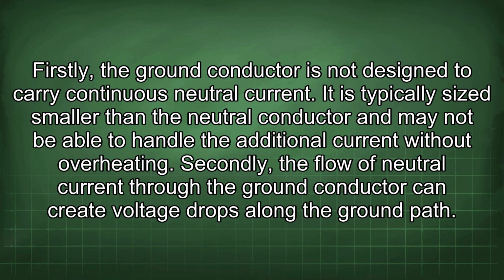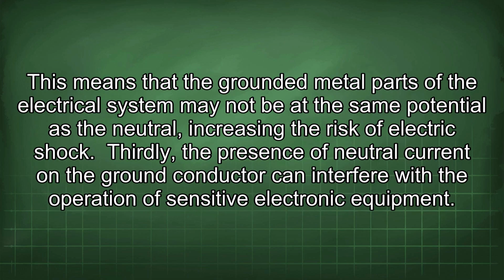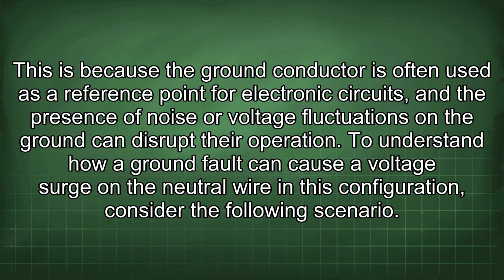Firstly, the ground conductor is not designed to carry continuous neutral current. It is typically sized smaller than the neutral conductor and may not be able to handle the additional current without overheating. Secondly, the flow of neutral current through the ground conductor can create voltage drops along the ground path. This means that the grounded metal parts of the electrical system may not be at the same potential as the neutral, increasing the risk of electric shock. Thirdly, the presence of neutral current on the ground conductor can interfere with the operation of sensitive electronic equipment. This is because the ground conductor is often used as a reference point for electronic circuits, and the presence of noise or voltage fluctuations on the ground can disrupt the operation.